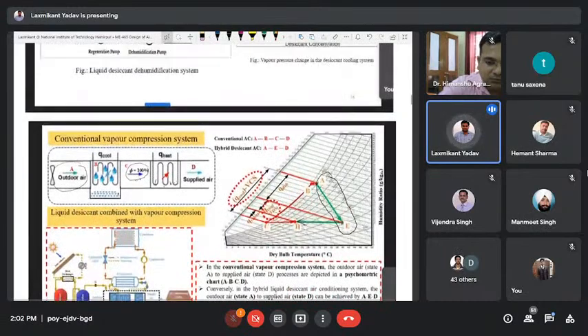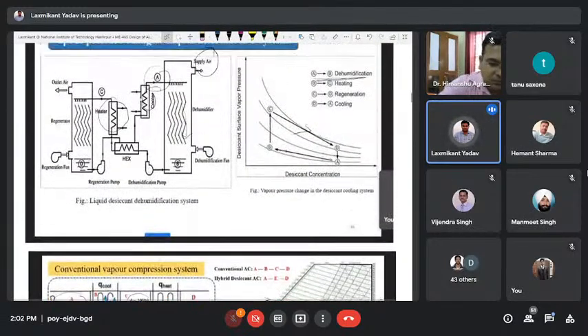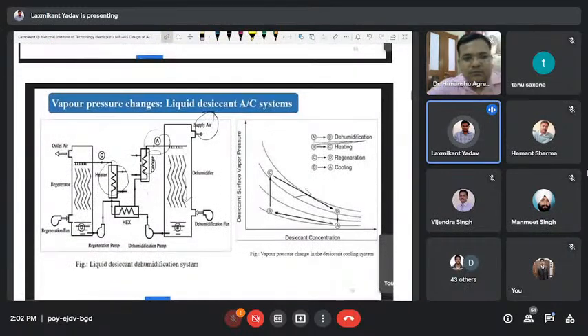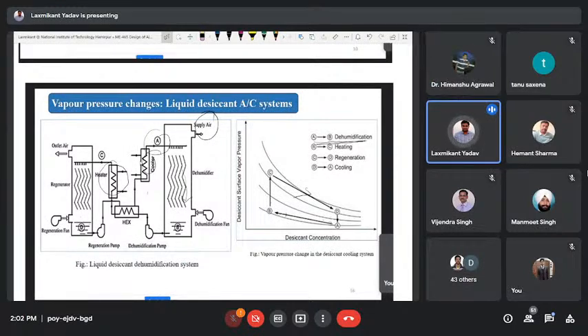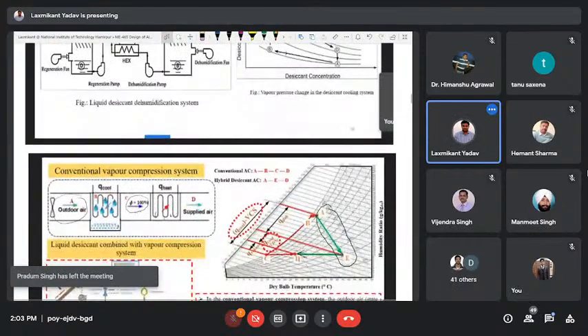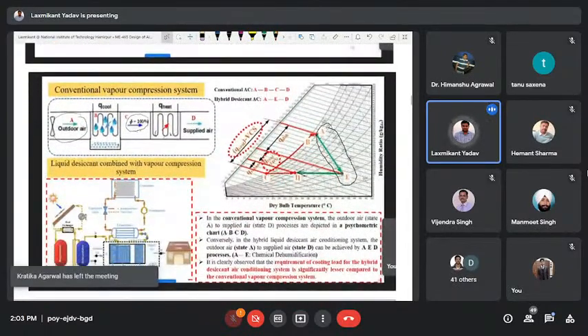Clear? Another disadvantage of liquid desiccant is that there is carryover loss. When there is absorption, some particles of lithium chloride or lithium bromide also enter into the room. That is the carryover of the liquid desiccant. Similarly, during regeneration, some liquid fraction of lithium chloride or lithium bromide also comes out to the atmosphere, so it may also pollute the atmosphere. So this is one of the disadvantages, the carryover loss.